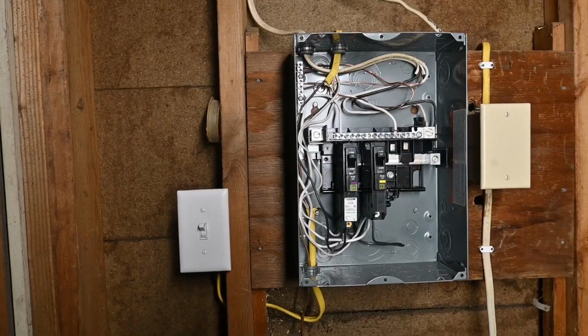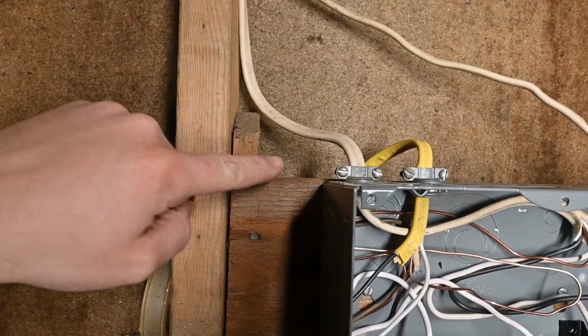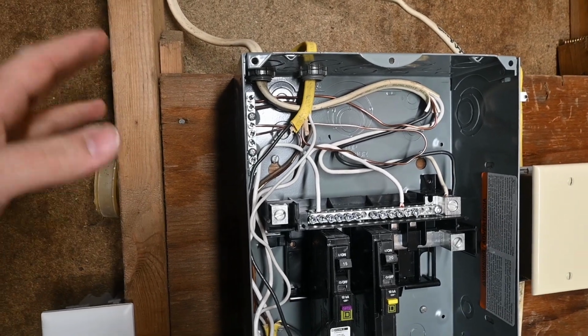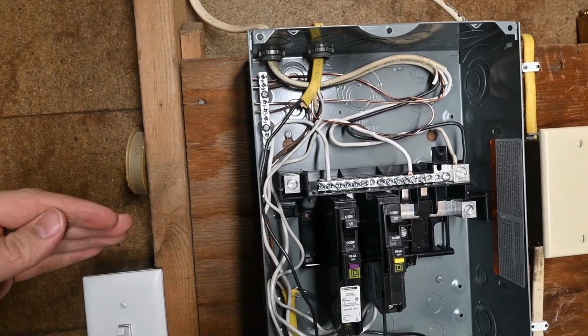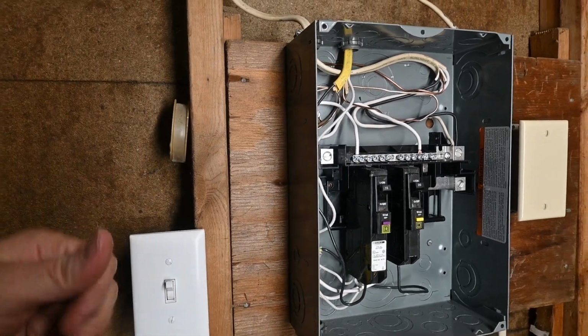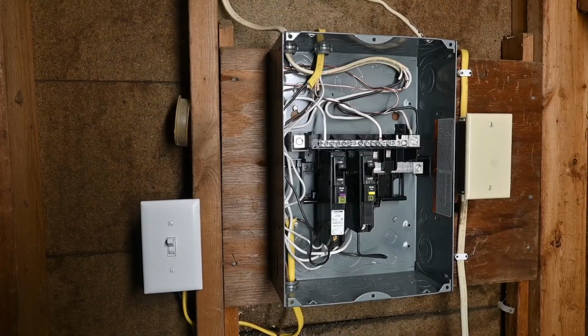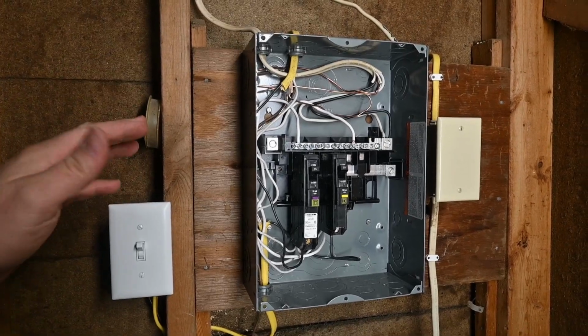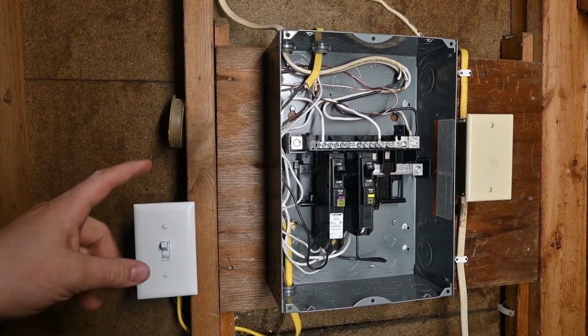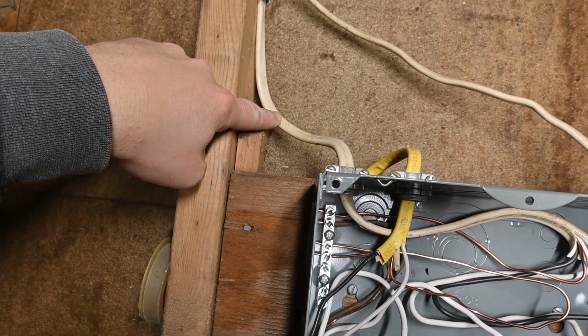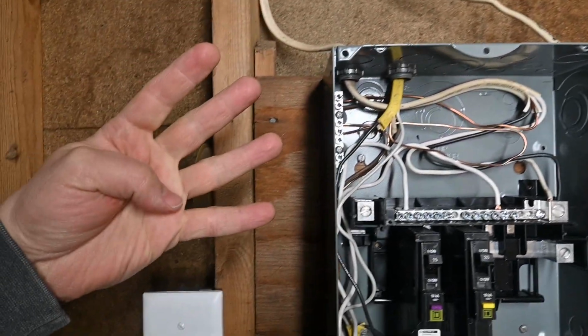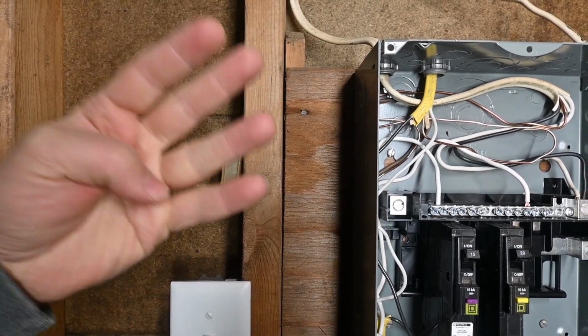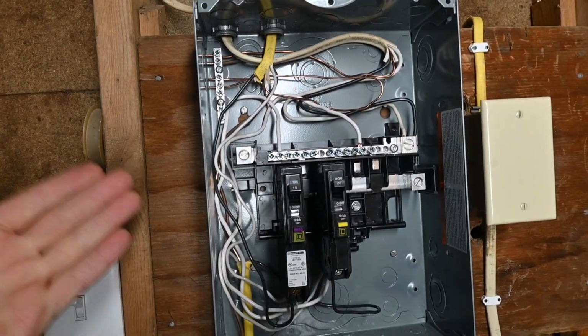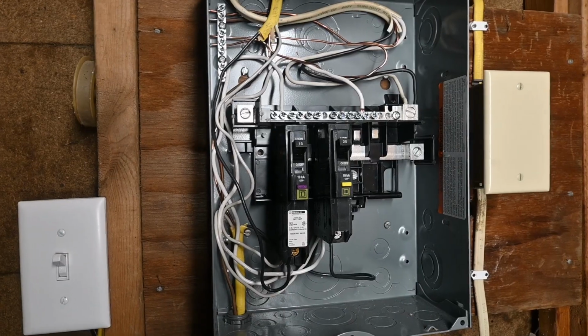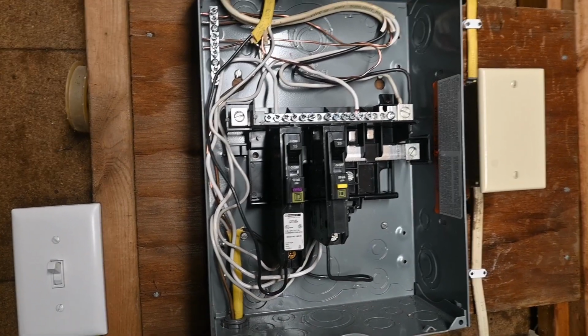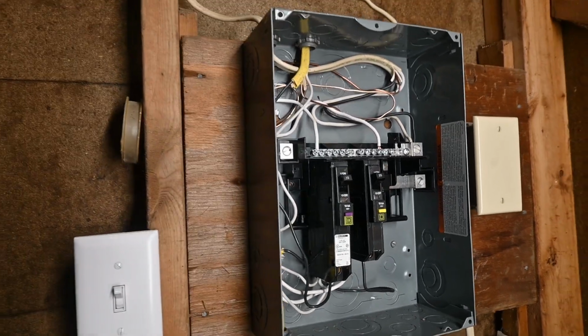In this particular case, with it being a single 20 amp circuit feeding this panel, I'm really not concerned that this is going to create a significant imbalanced load back on the main panel in the house. The whole idea here is that if they ever need a welder or a big air compressor or something else out here, this cable that's feeding the panel will get replaced with a 4-conductor cable, the 2 hots, neutral, and a ground that will allow it to have a proper 240 volt setup. Until then, these couple of circuit breakers is all that's going to really be needed for the use case of this particular panel.